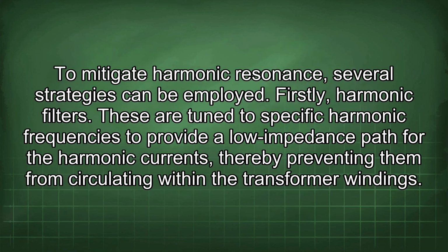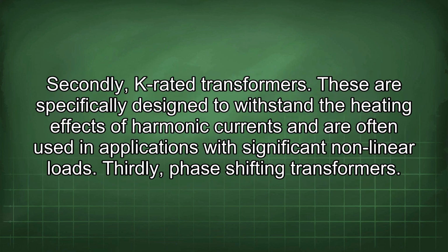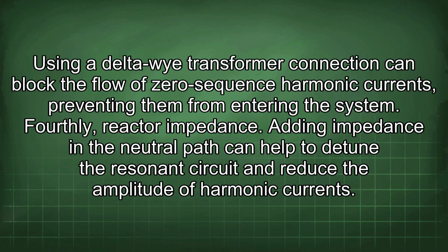To mitigate harmonic resonance, several strategies can be employed. Firstly, harmonic filters. These are tuned to specific harmonic frequencies to provide a low impedance path for the harmonic currents, thereby preventing them from circulating within the transformer windings. Secondly, K-rated transformers. These are specifically designed to withstand the heating effects of harmonic currents and are often used in applications with significant nonlinear loads. Thirdly, phase-shifting transformers. Using a delta-wye transformer connection can block the flow of zero-sequence harmonic currents, preventing them from entering the system. Fourthly, reactor impedance. Adding impedance in a neutral path can help to detune the resonance circuit and reduce the amplitude of harmonic currents.